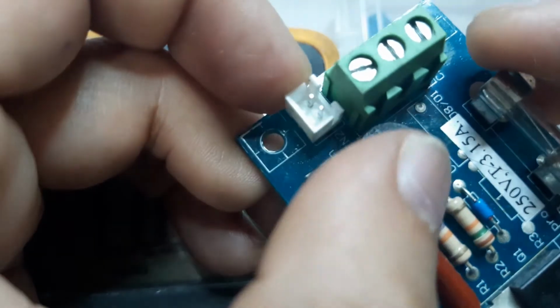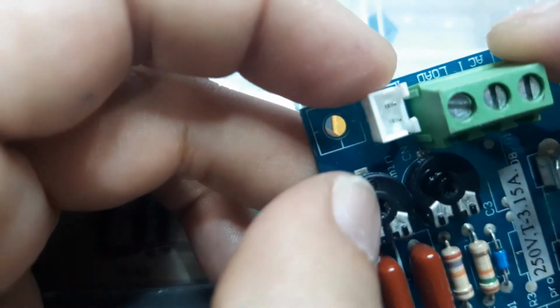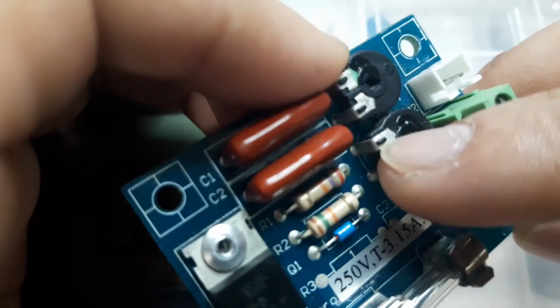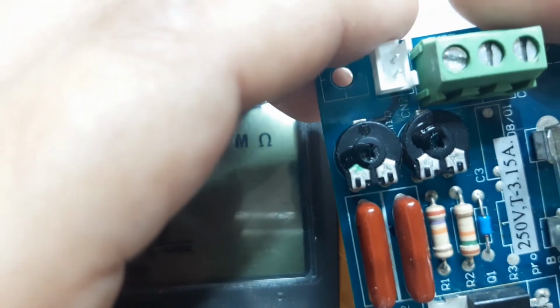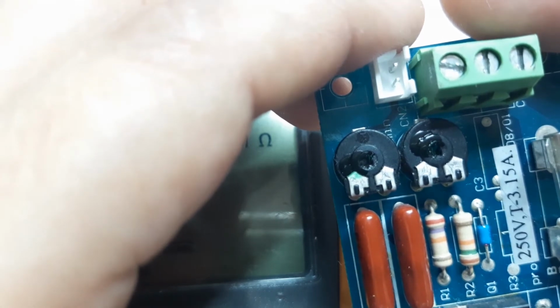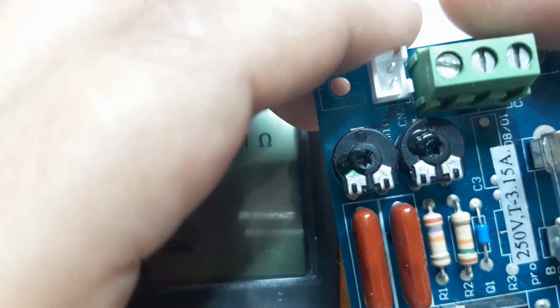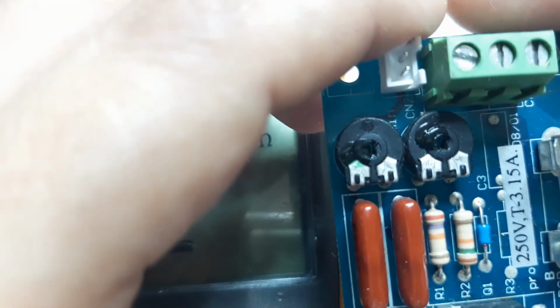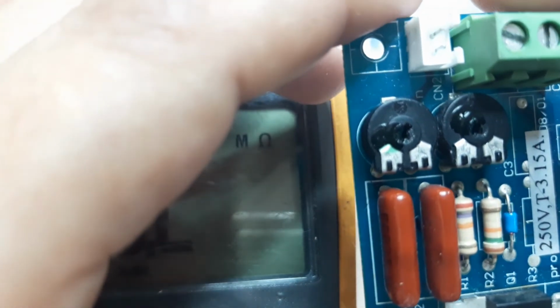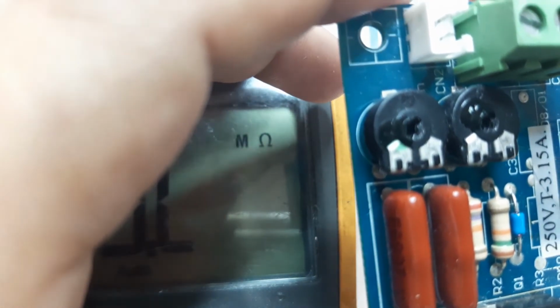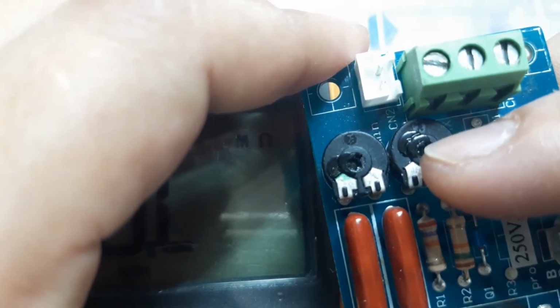So let's try to remove this one. It's written here minimum, and it's written here maximum, max. So most probably this trimmer is used for calibration of the speed, because the centrifuge has a certain speed, I mean the RPM. This is used to calibrate the RPM, like if you have a setting like 4000 RPM, 3500 RPM. So I think this is used to calibrate.